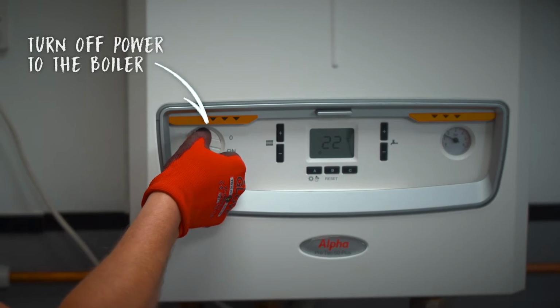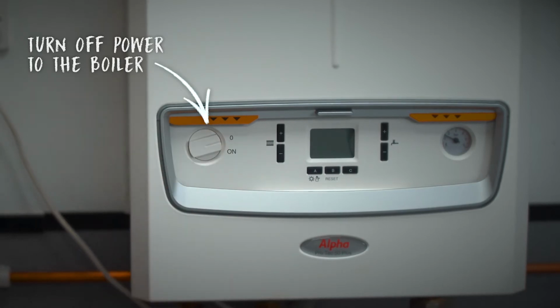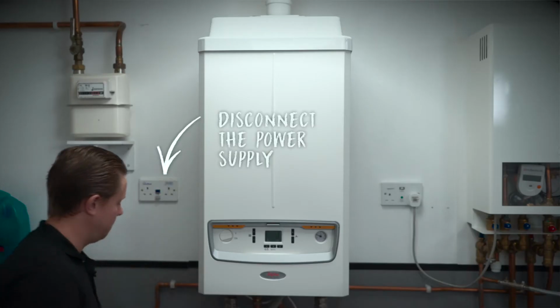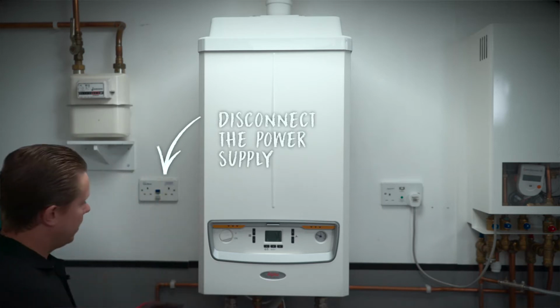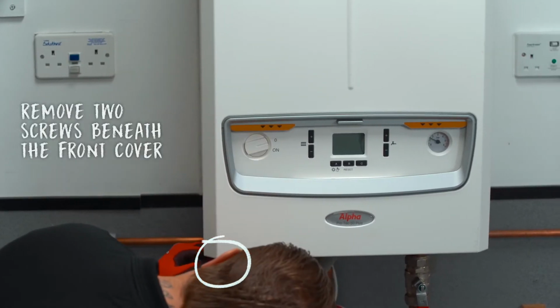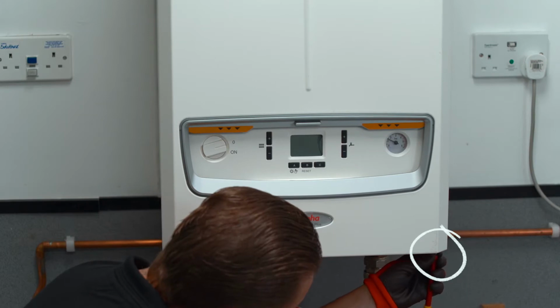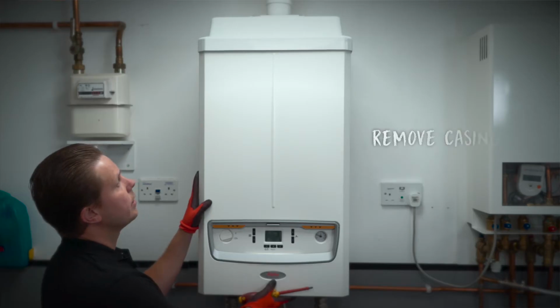Start the service by turning off the power to the ProTec Plus boiler and then isolate the power supply, or remove the lock-off fuse spur. Remove the two retaining screws at the bottom left and right of the appliance and take off the front casing.